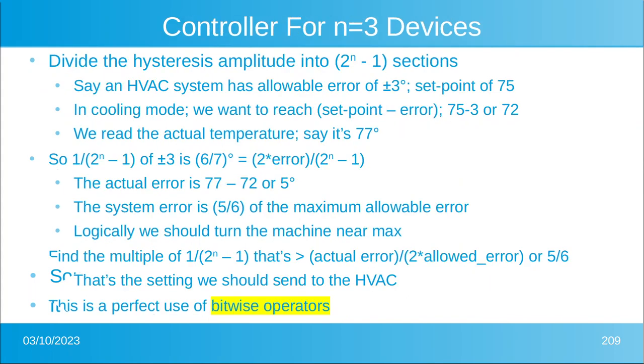For a three-device controller, the devices divide the hysteresis amplitude into seven sections — not eight — because zero doesn't actually do anything in our hysteresis. For example, say an HVAC system has an allowable error of plus or minus three degrees with a set point of 75. In cooling mode we want to reach a minimum of 72 degrees, then let it warm up to 78 degrees, then turn on again and cool back down to 72.